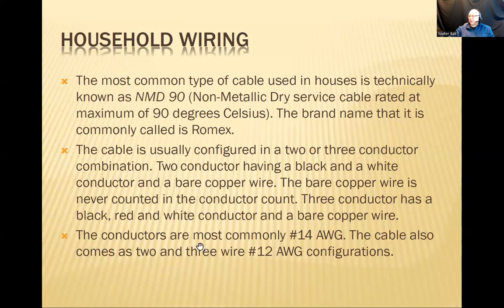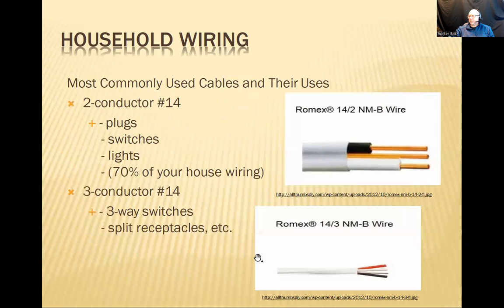The conductors are most commonly 14, and you see American Wire Gauge. When you see that, you just read gauge, 14 gauge. You don't read number 14 AWG, or for sure you don't read hashtag 14. So just skip that. It's just 14 gauge. The cable also comes as 2 and 3 wire in 12 gauge configurations. Depending on if we need more current to be passing through the cable, you use a thicker cable, which means you go down with the gauge. Right? Household wiring, most commonly used cables and their uses.